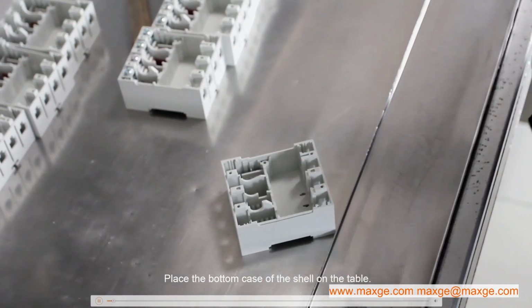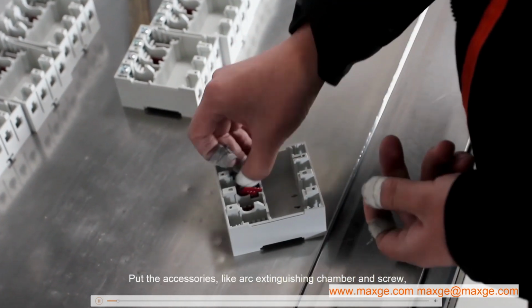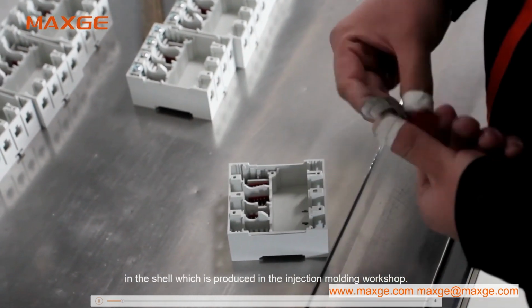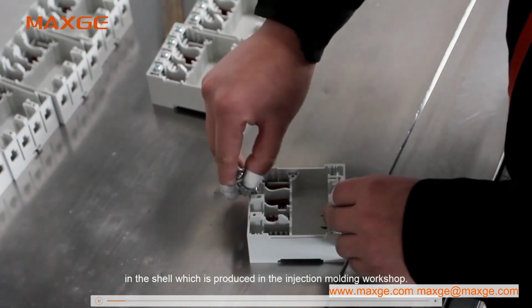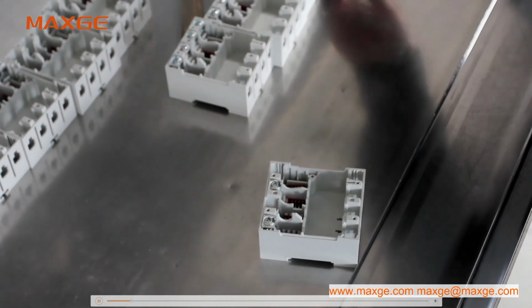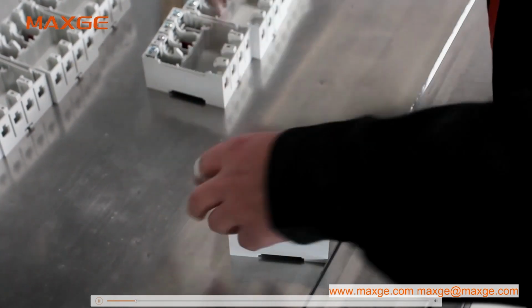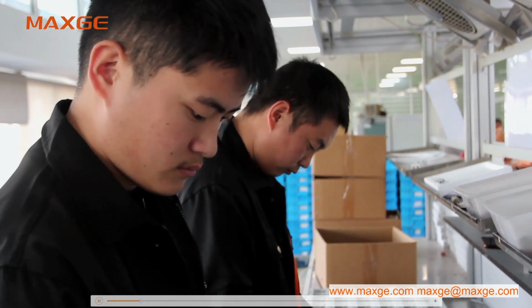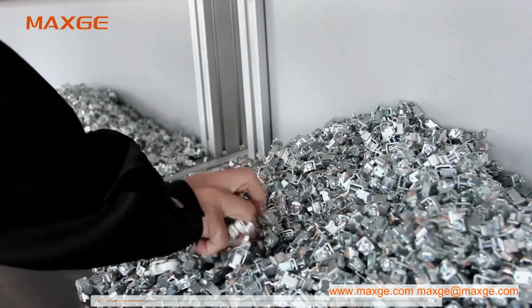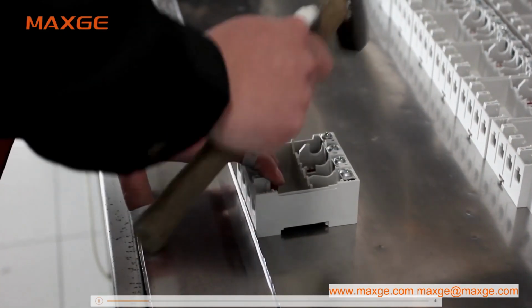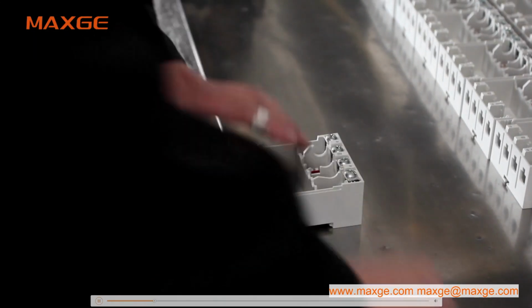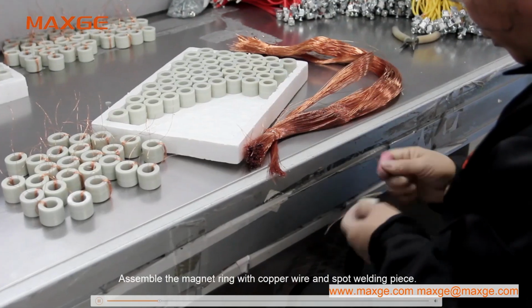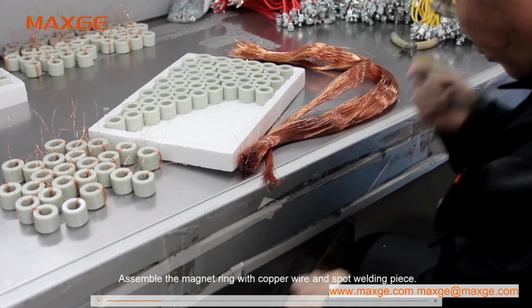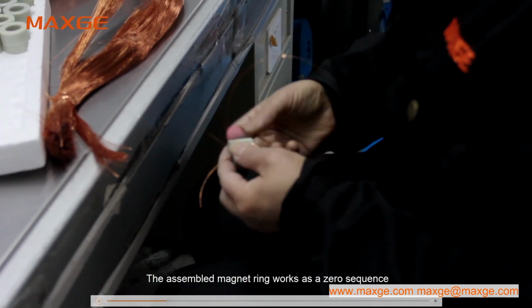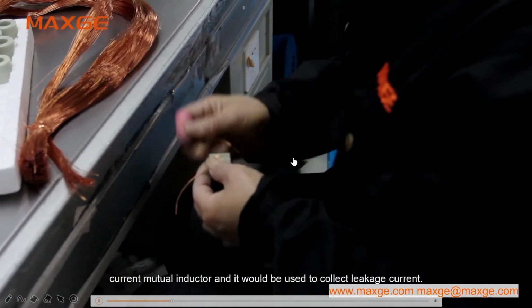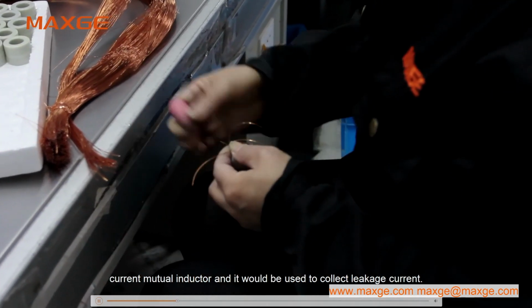Place the bottom case of the shell on the table. Put the accessories, like arc extinguishing chamber and screw, in the shell which is produced in the injection molding workshop. Assemble the magnet ring with copper wire and spot welding piece. The assembled magnet ring works as a zero-sequence current mutual inductor, and it would be used to collect leakage current.